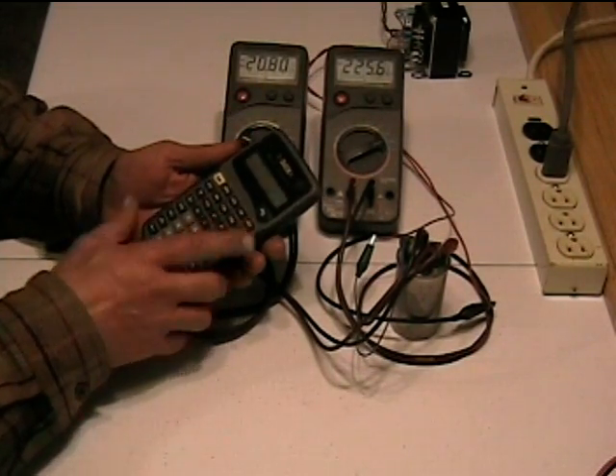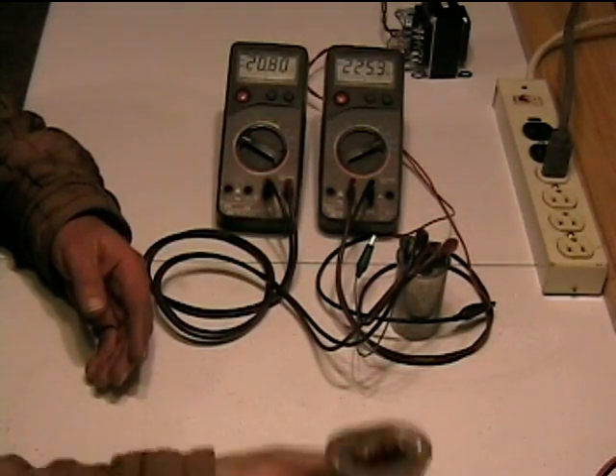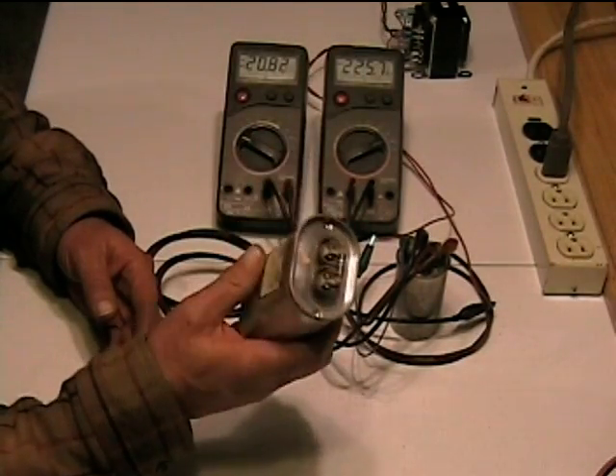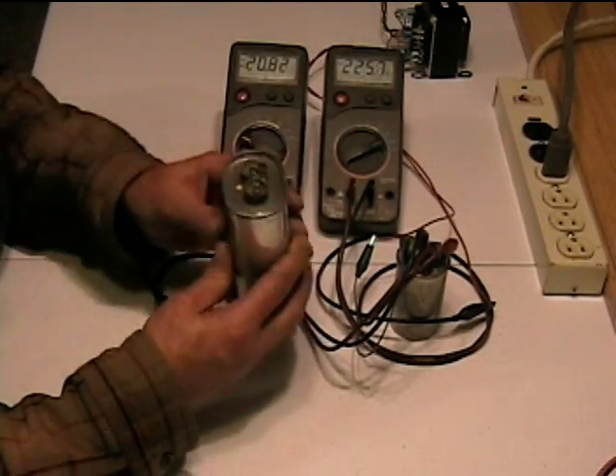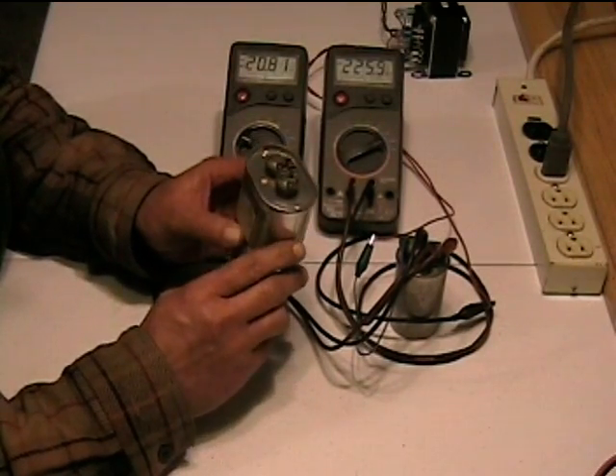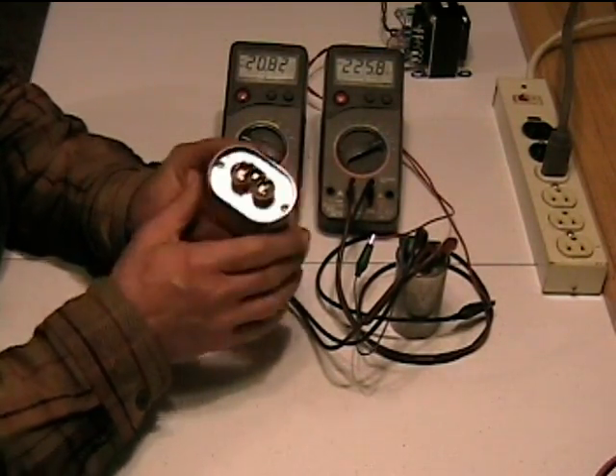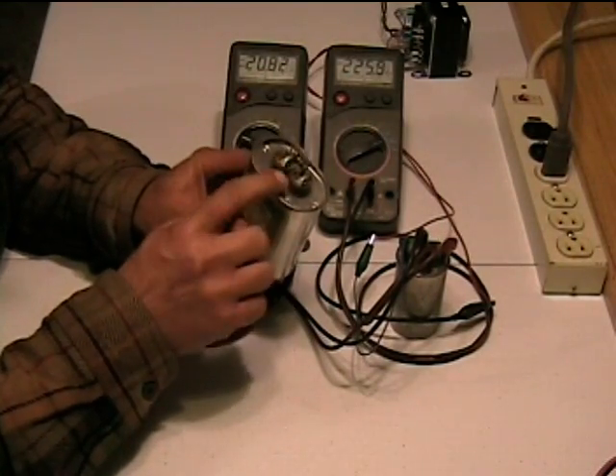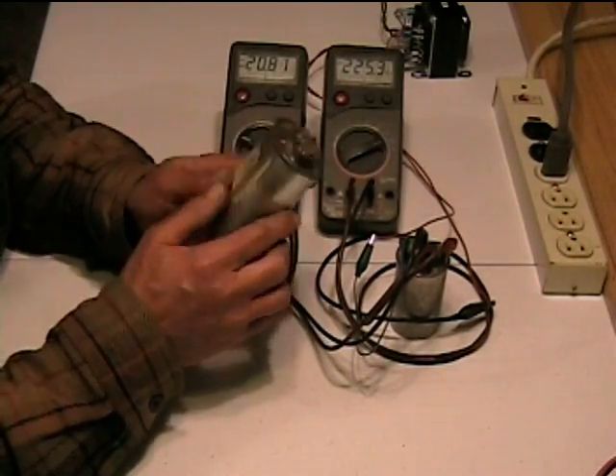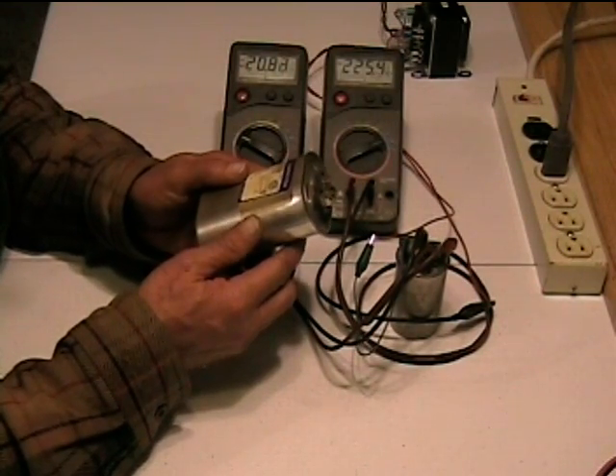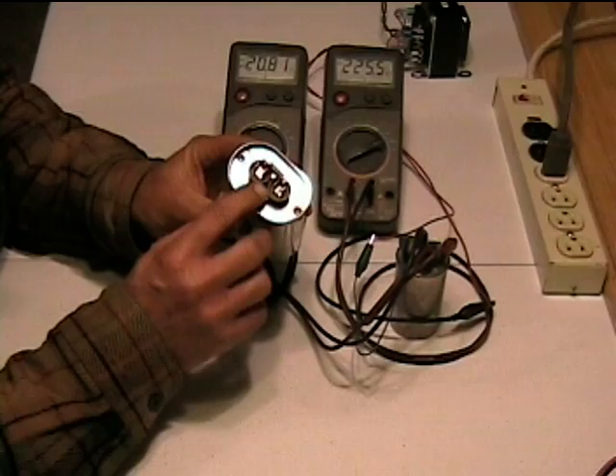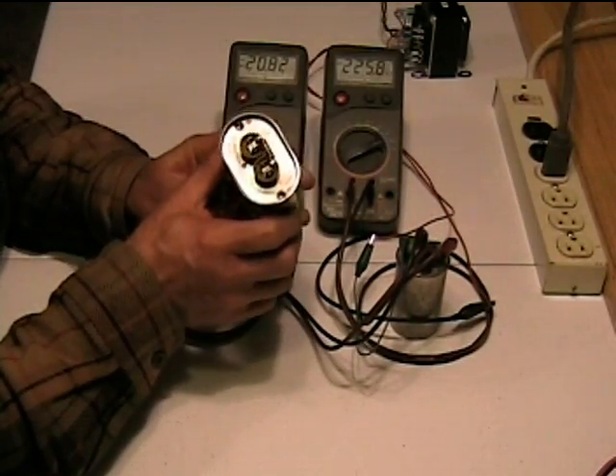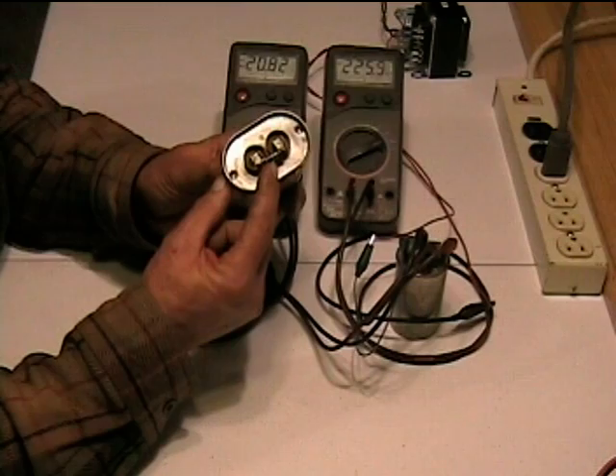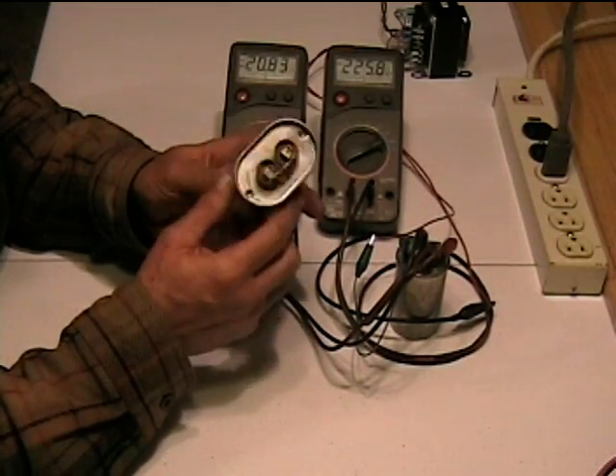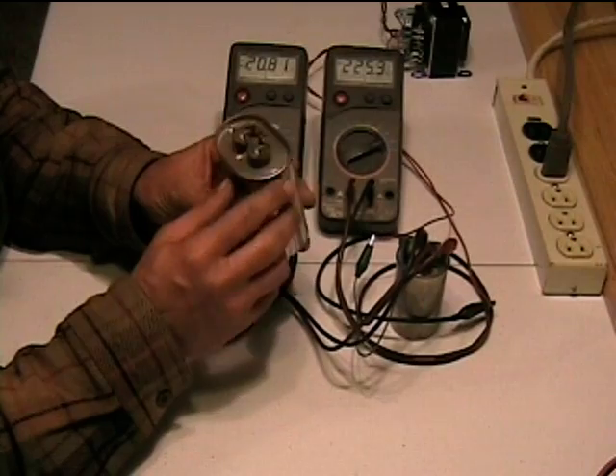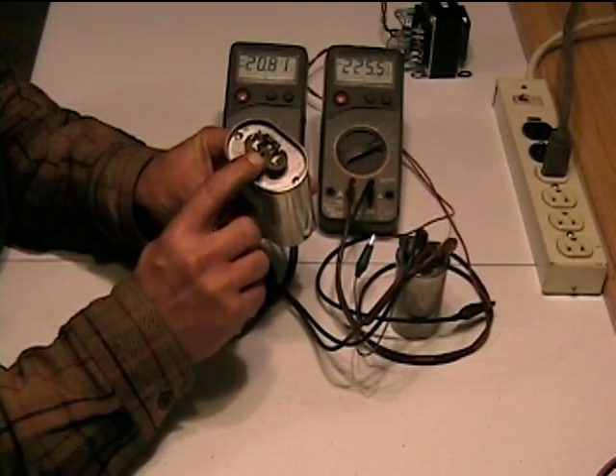That's all very easy. A few cautions about capacitors. This is an energy storage device, so when you go to remove it from whatever device you're bringing it out of, whether it's a light fixture or a motor or whatever, short across the two terminals, because this thing can hold a charge. It could be several hundred volts, so short across it so you don't get hurt if you touch the terminals. Usually that isn't a problem if the motor's in good shape. It will have discharged it. This came out of a lighting fixture, a metal halide fixture. It has a bleeder resistor wired across the terminals, but the resistor could have gone bad and there could be several hundred volts across there. So always short across the terminals to discharge it.